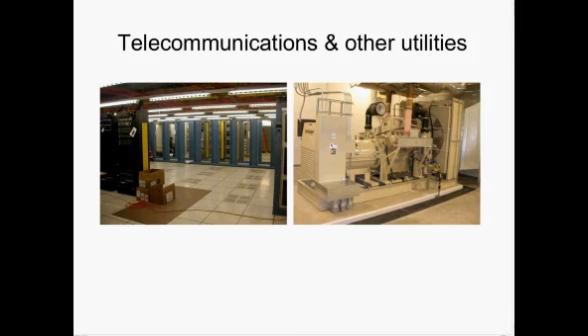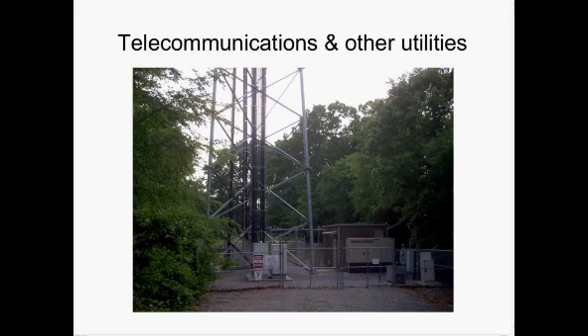These UPS systems are expensive to install and maintain. The size is limited to the power requirements of the telephone switching center, and the diesel engine generator set is sized accordingly. The same is true for cell phone communications. A smaller UPS system is employed at each cell tower. These UPS power supplies are backed up by engine-driven generator sets.